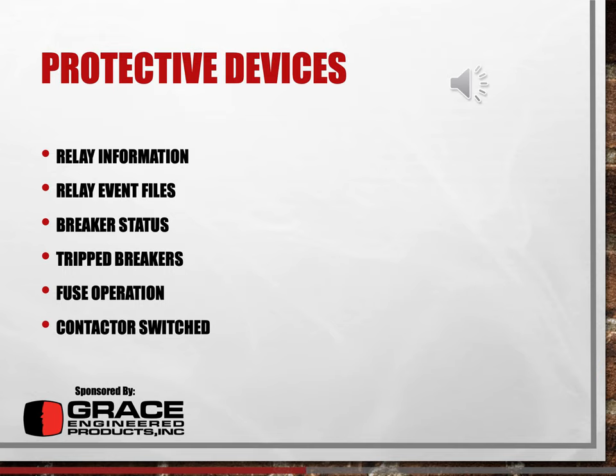You can actually cut open the fuses and tell by the fulgurite inside the fuses, or estimate the type of fault current that the fuse conducted to trip the fuse. I used to work for a fuse manufacturer, and we used to do that all the time when diagnosing fuse failures or fuse operations. And then you also want to know if the contactor switch or any auxiliaries or relays or programmable logic controllers change state.